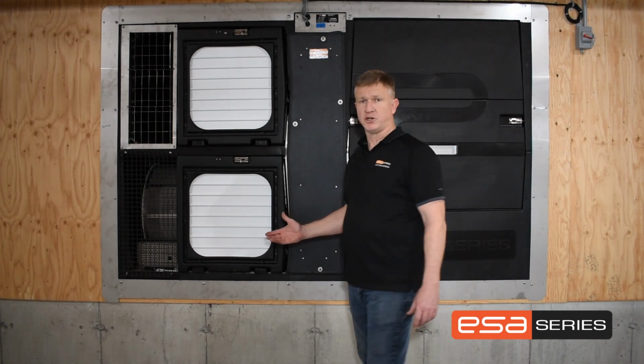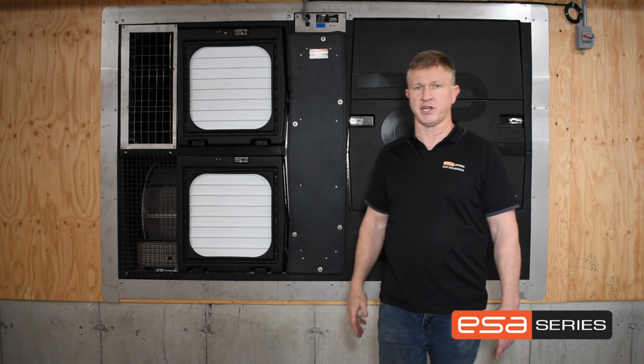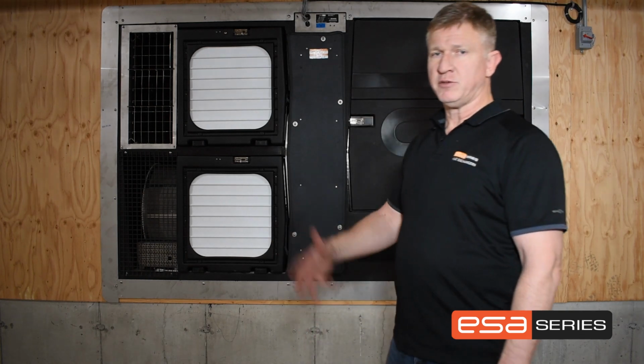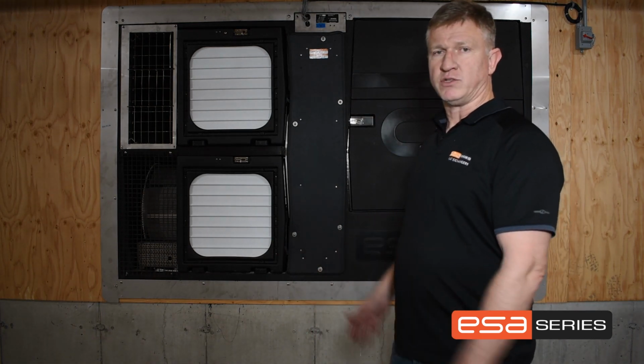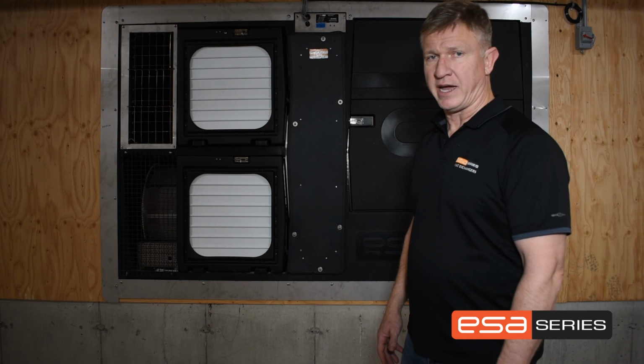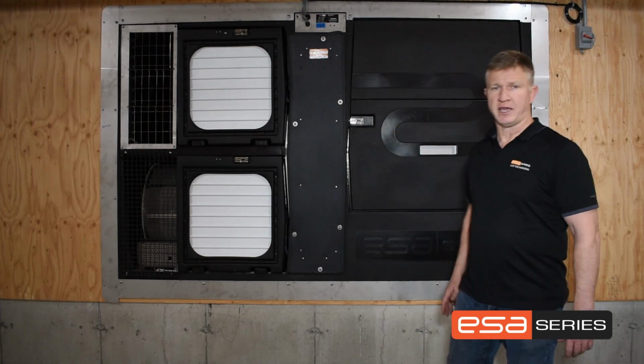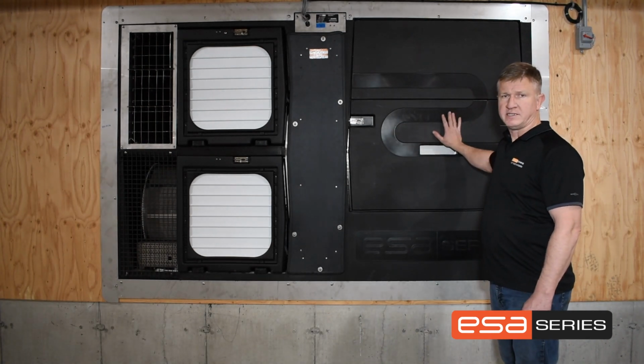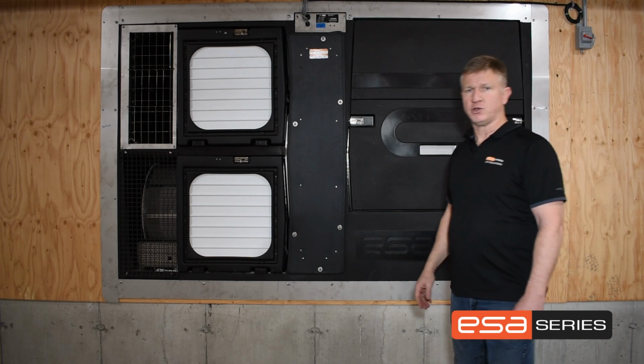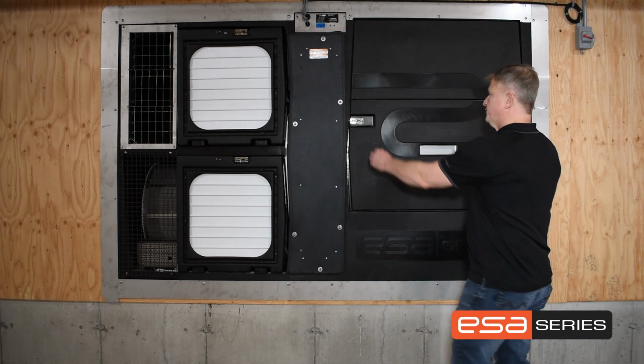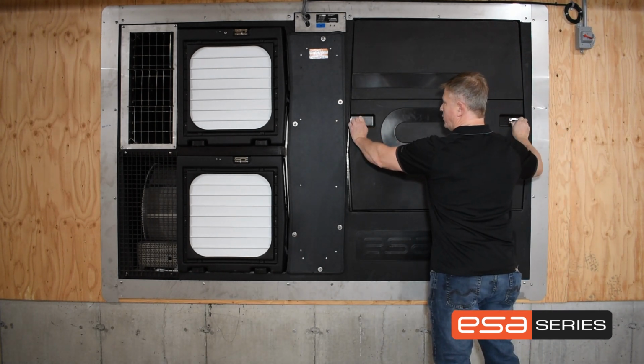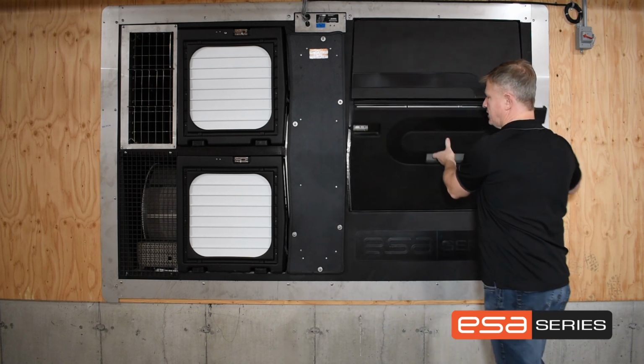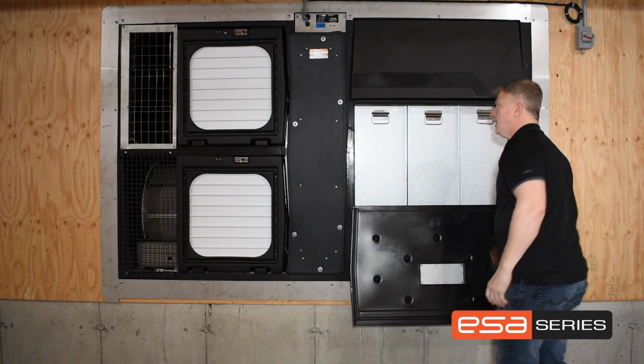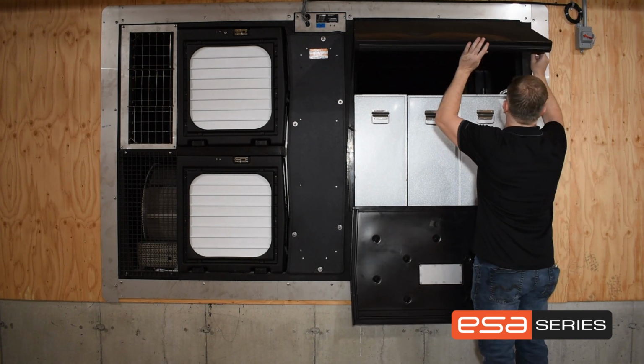So the heat exchanger is bringing fresh air from outside into the barn, and taking out stale air and exhausting it outside. It's exchanging that air through a core that's inside here, and I'll show you what the core looks like. To open up the door, you have these latches on the sides. You open them up and you can see the core inside.